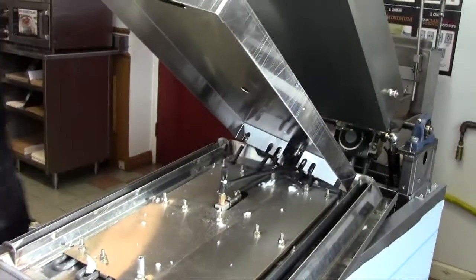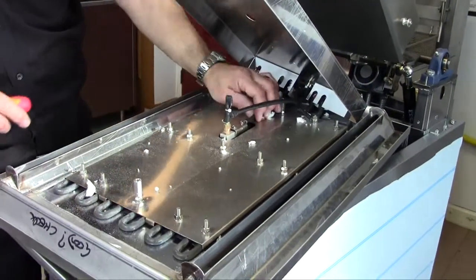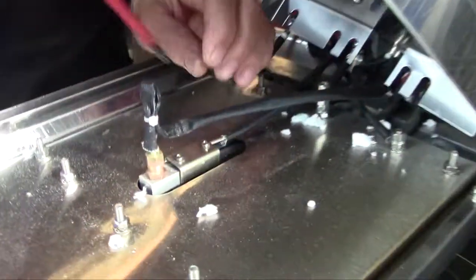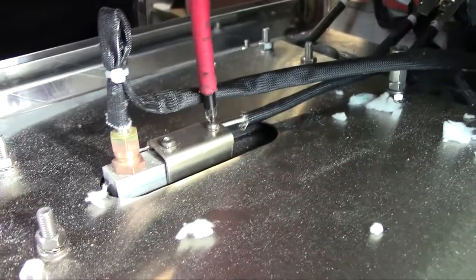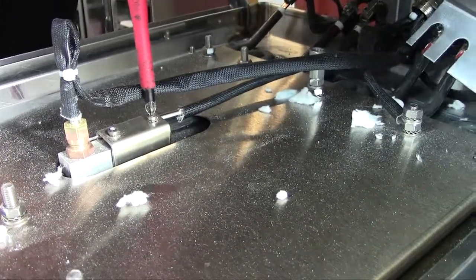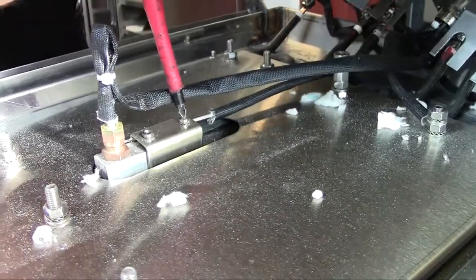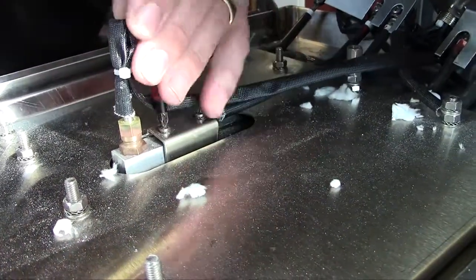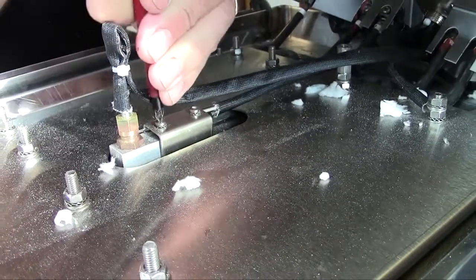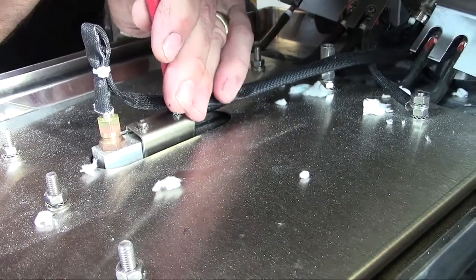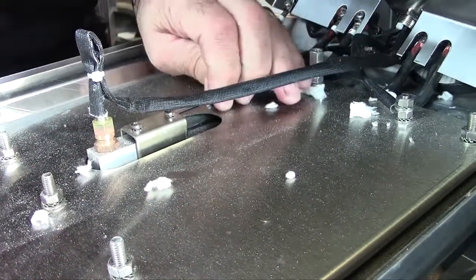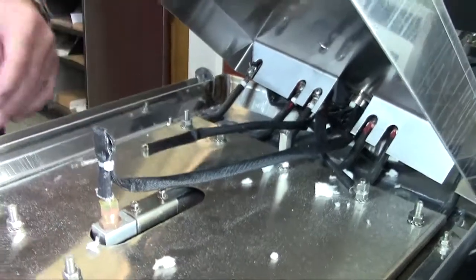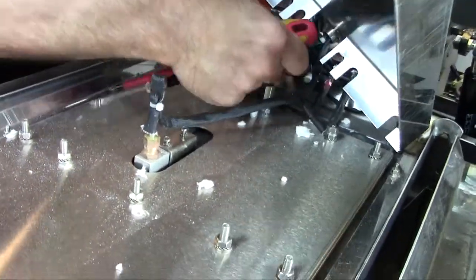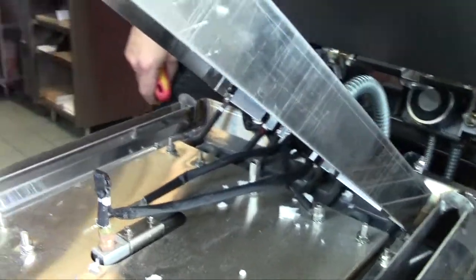Take your insulation out of the way. Right, the high limit bulb end's fitted into here, so you need to unscrew these. Loosen these 2 screws like so, and then pull the probe out. Then all you do is feed it back, it goes underneath there, and then you remove the old one by taking these 2 screws out.